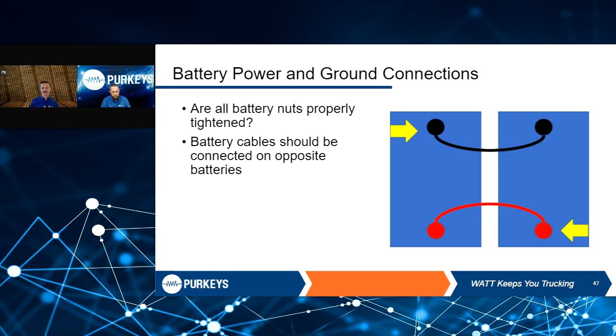Circling back to that poll question, anytime you have a major charging source or discharge from a group of batteries, you do want to stagger those positive and negative connections. That's always going to be the best practice in these scenarios. With the Purkeys system on its own, the output from that charger, typically around 20 amps or so, should still be staggered. Not the absolute end of the world if it's not, but I'd say that's about the threshold. Anything more than that, you really should always be staggering those connections. If you see one while doing PMs or swapping out batteries, make sure you're using that best practice, staggering positive and ground across the battery bank.